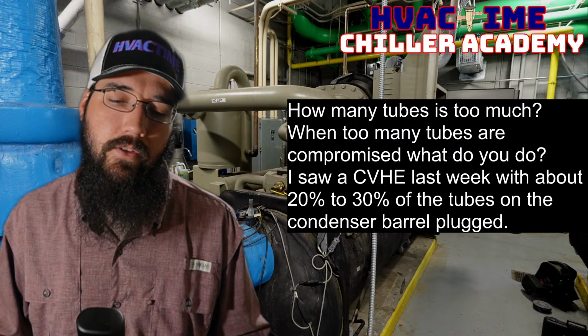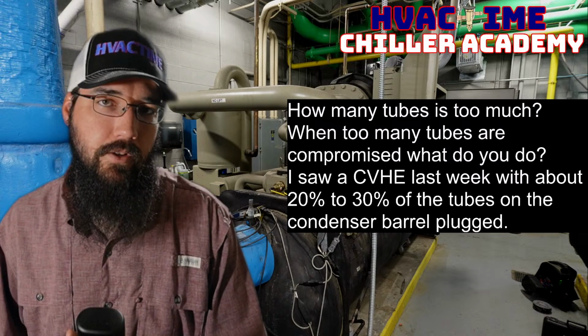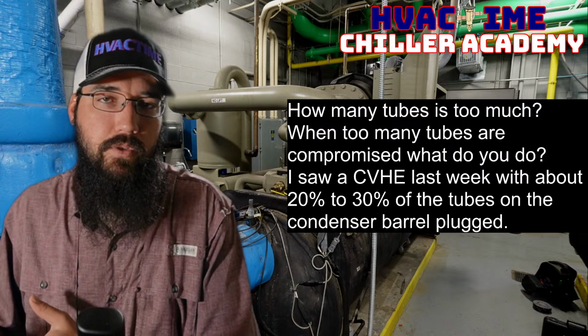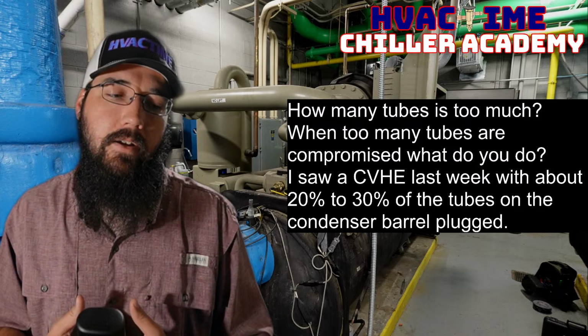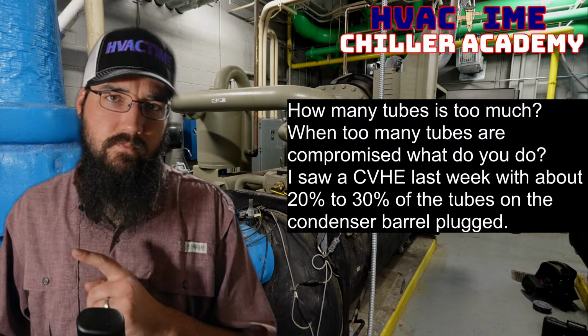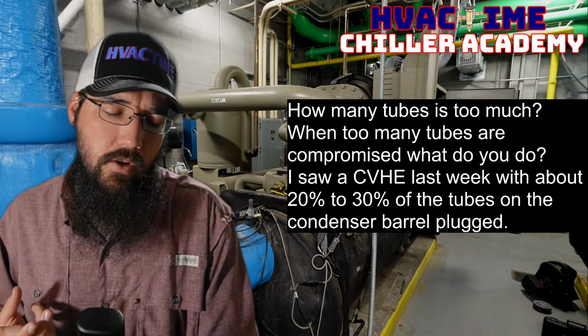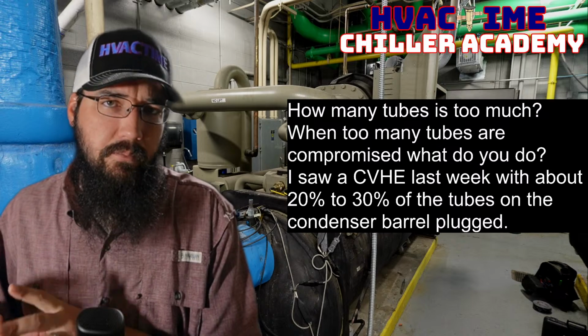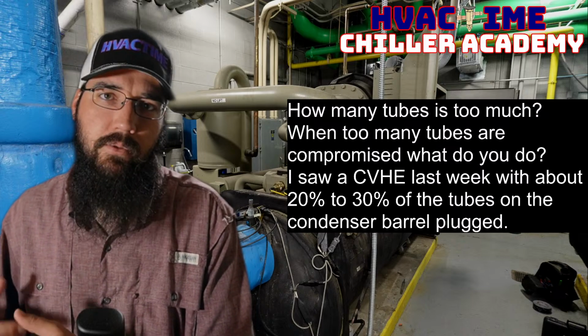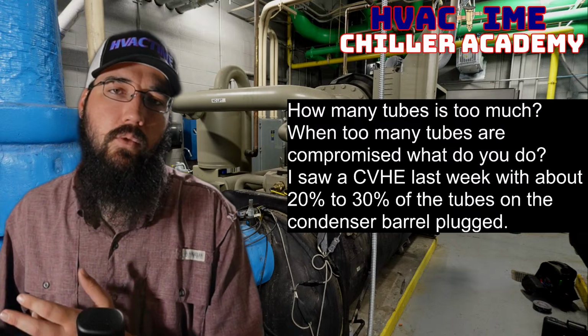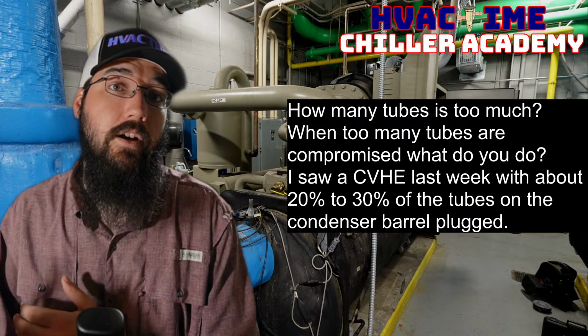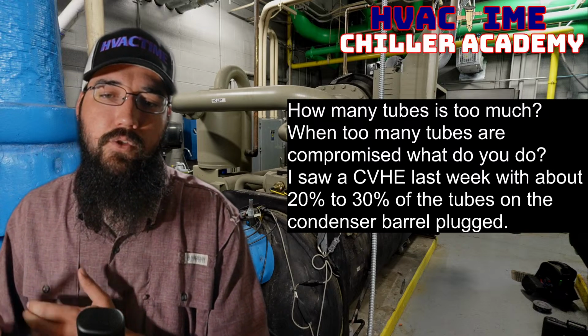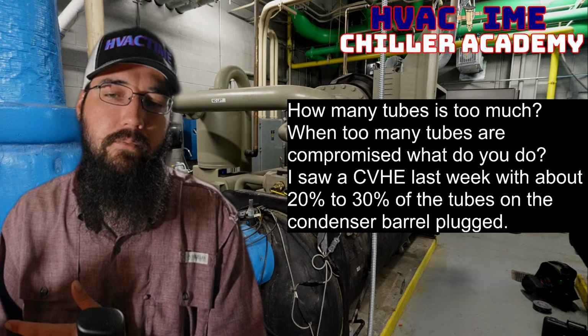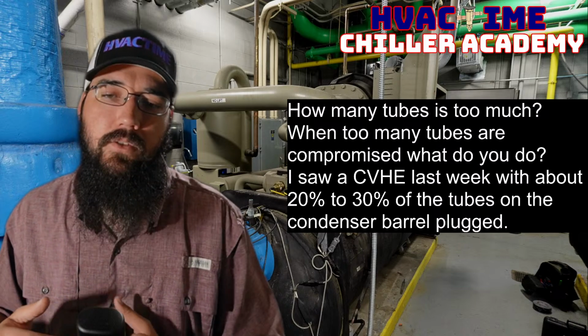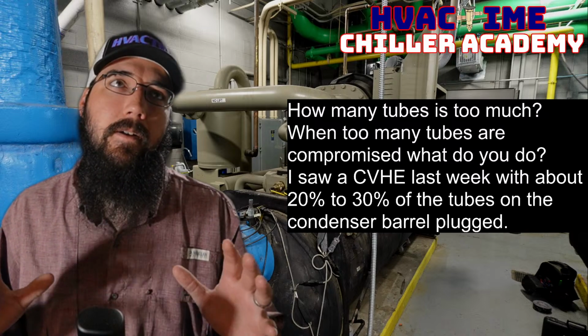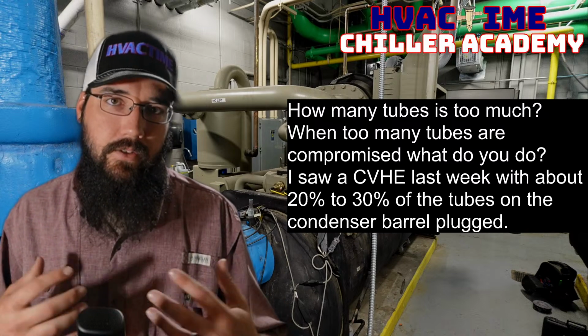Immediate red flags. Now, the question becomes what's going on in this particular loop that we're having that many tubes need to get plugged in the first place? Are we having a water side issue? Are we too high on our GPM? Is the chemical balance not correct, and we're starting to heavily corrode the tubes themselves? Like, what other conditions are possibly going on that could be causing the tubes to need to be plugged so often?